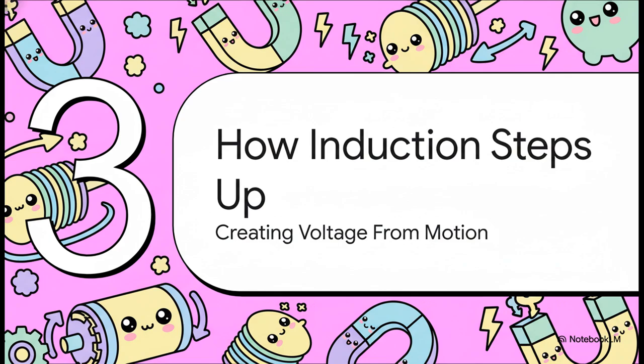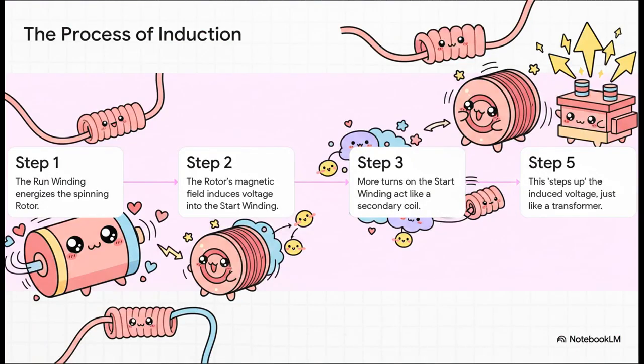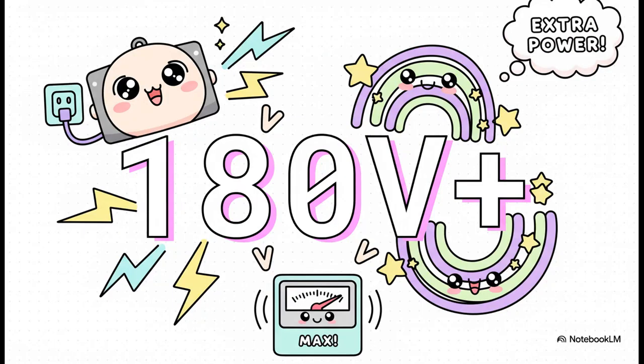So, how does this little temporary transformer actually build up a higher voltage? Well, it all comes down to a really cool principle called magnetic induction. Okay, here's the play-by-play. The run winding creates a magnetic field, and that gets the rotor spinning. Now, as that rotor gets up to speed, its own magnetic field starts expanding and sweeping across the wires of the start winding. And because that start winding has way more turns of wire, this interaction doesn't just create a voltage, it amplifies it, stepping it way, way up. And the result is honestly pretty amazing. A motor that's just running on a standard 120-volt circuit can suddenly have over 180 volts pulsing through its start winding. It's literally creating its own extra power right on the spot.